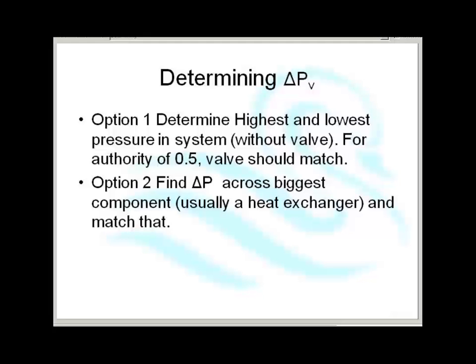The first way, which I haven't even listed up here, is by looking at every single piece of pipe and every single elbow and every single bend and calculating the pressure drop in that particular item and adding them all together. Now, that's a horrific job and takes forever. The second system, if you can possibly do it, is to build the system and start the pump and see what the pressure drop is. Easy, really, just measure it.